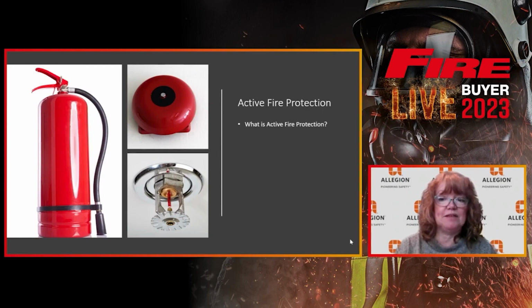Sprinklers are quite sophisticated and are designed to be heat sensitive so that the sprinkler only activates when temperatures rise to fire-induced temperatures. Fire extinguishers are a handheld active fire protection device. There are 5 classes of extinguishers, classes A to E. A being used on ordinary combustibles like wood, rubber, paper, as well as some plastic materials. Some extinguishers also have multi-classes of use.